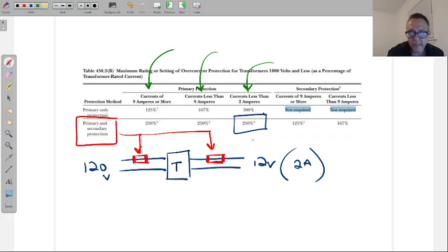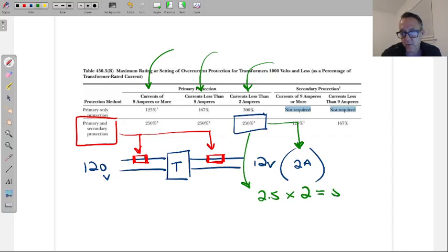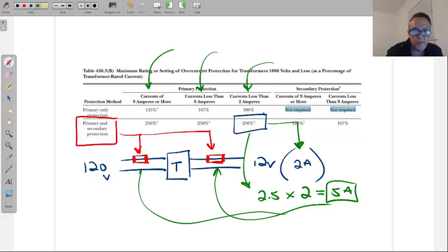This fuse has to be 250% larger than 2 amps. Now, that's not a lot for 2 amps, but it is a little bit bigger than 2 amps, not by a lot. But 2.5 times, that's how we would do that, 2 equals 5. All right, the math would be 2.5, 250 converted, times 2 amps equals 5 amps. So this fuse and this fuse need to be 5 amps to protect this circuit.